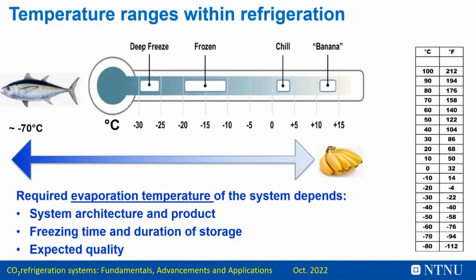So what temperature ranges are we talking about? For CO2 applications, we can reach levels, I will show you in a minute, down to -50, not to -70, but then we need to do a cascading system, but that's not the topic of today. But we can work from -50 to plus whatever is needed, but it's very important to understand, of course, the evaporating temperature. It depends very much on the system architecture and the product. What do we want to do?